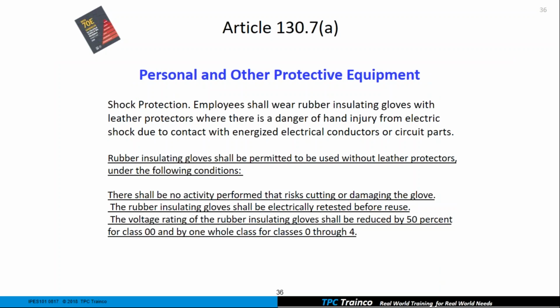This is also, in my opinion, a great change. Generally speaking, employees have to wear rubber insulating gloves with leather protectors. So we know that. But what's new? Rubber insulating gloves shall be permitted to be used without leather protectors if we can satisfy these conditions. No activity that's going to risk cutting or damaging the glove. The gloves have been electrically retested after I do this, and the voltage rating of the rubber insulating gloves shall be reduced by 50% for class 00 and 1 whole class for classes 0 through 4. So because we don't have the leather protector on, they're going to reduce the rating of that glove. If I took a class 0 glove, which is rated for 1,000 volts AC, and I was going to use it without the leather protector, it would now be good for a class 00, which is 500 volts AC.